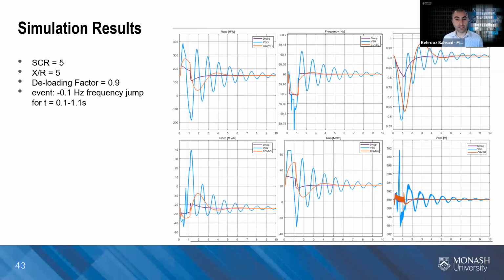And one challenge, by the way, that we've got in wind farms is to make sure that the torque that is requested from the turbine is not seeing any excessive transients, because it can cause some mechanical problems for the turbine, some fatigue problems. So we need to also make sure that all the transients are within the capabilities of the turbine from a mechanical point of view.